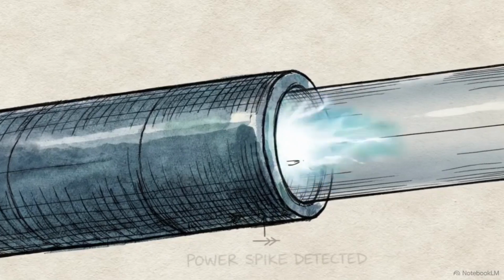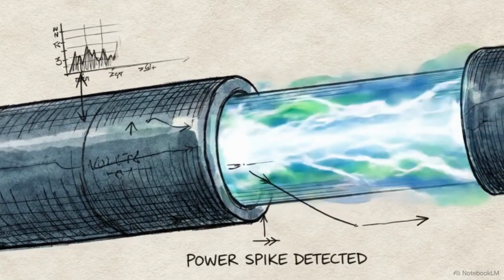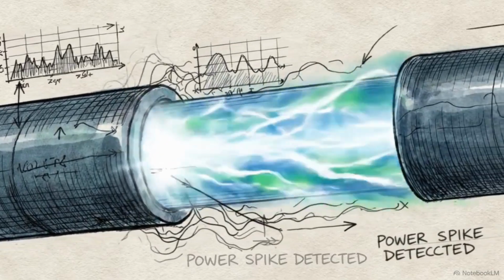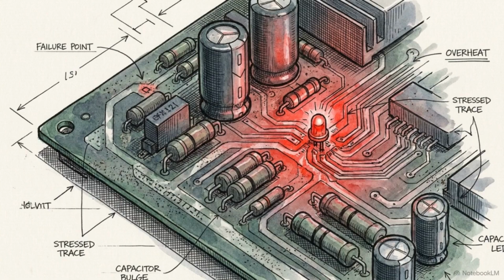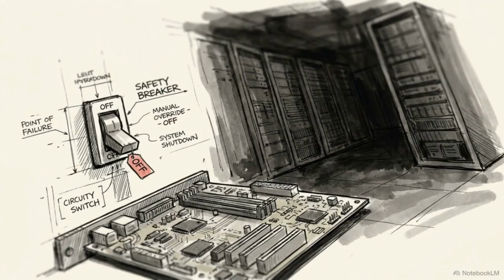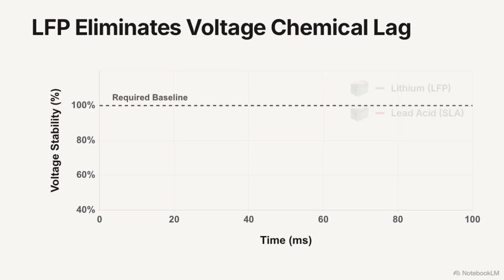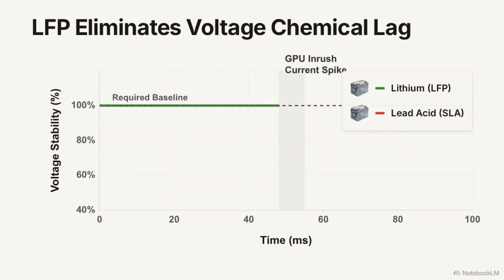When a cluster of GPU or AI servers boots up, they pull violent power spikes known as inrush current. Older UPS inverter boards cannot react fast enough to these step-load demands. They often interpret a rapid GPU spike as a short circuit, causing the UPS to cut power to protect its own internal components. Lithium iron phosphate handles deeper discharges and rapid cycling without the chemical lag seen in lead acid.